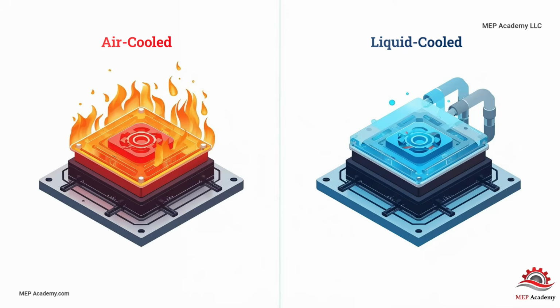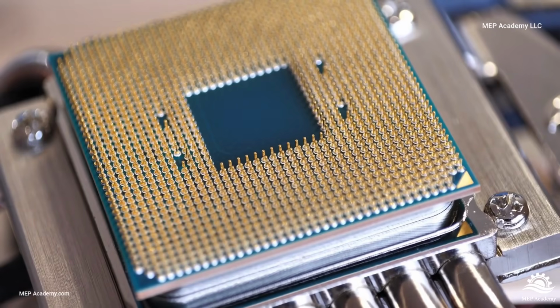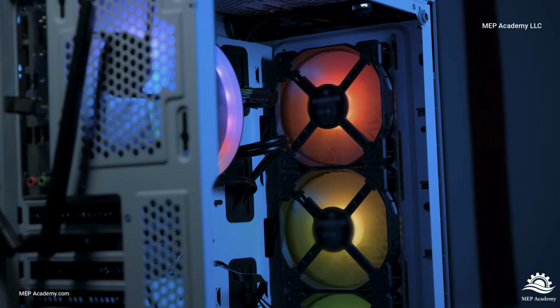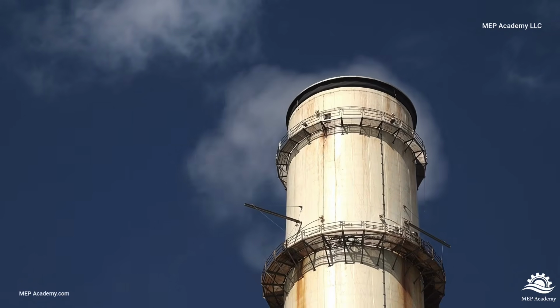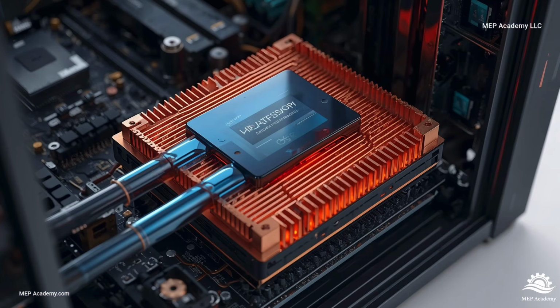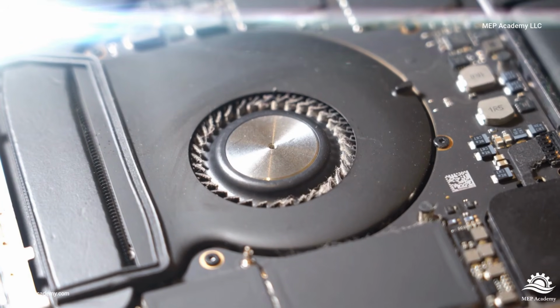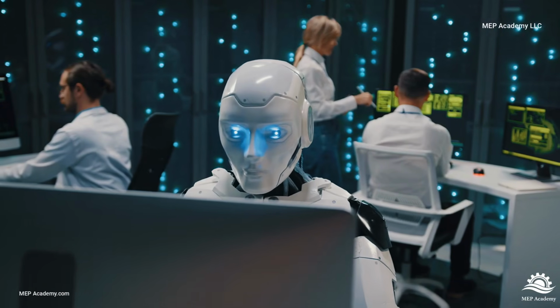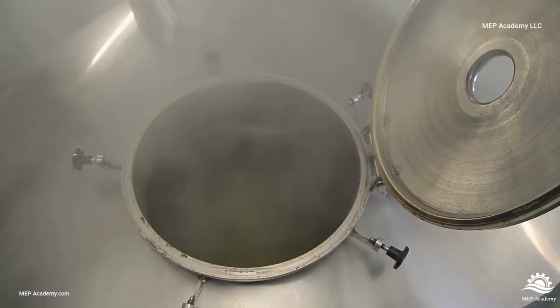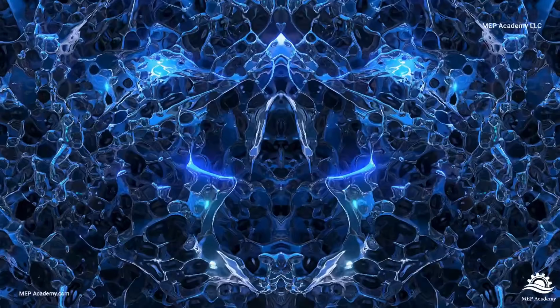Liquid cooling simply means using a liquid to remove heat from electronic equipment. Instead of relying entirely on air to transport heat away from processors, liquid is brought much closer to the source of the heat. The liquid absorbs the heat and carries it away where it can be rejected through the facility cooling system. The goal is simple: remove heat as close to the source as possible. The closer you get to the processor, the more effective the cooling becomes. Today, there are two primary approaches being used in AI data centers: direct-to-chip cooling and immersion cooling. Let's look at each one.